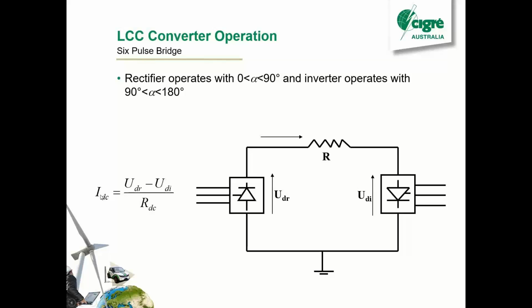And you can see here, we can then choose how much DC current we get through our transmission line by changing this voltage difference. So it's kind of like angle difference with AC transmission lines, but generally the way it's done is you hold your rectifier at your transmission voltage, and then you reduce it at your inverter depending on how much power you want to draw. So in our scheme, we'd hold our rectifier at 350 kV, and the inverter would be at some voltage lower than that, depending on how much power. So say 340 kV, that might be about 100 megawatts or something, and it can get down to about 330. It depends on your transmission line resistance, how far down it goes. So that's how you can control how much power you send with your firing pulses.